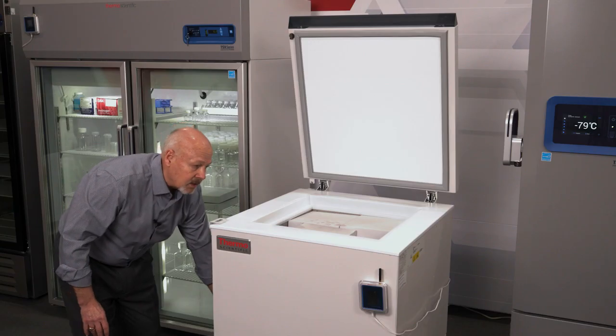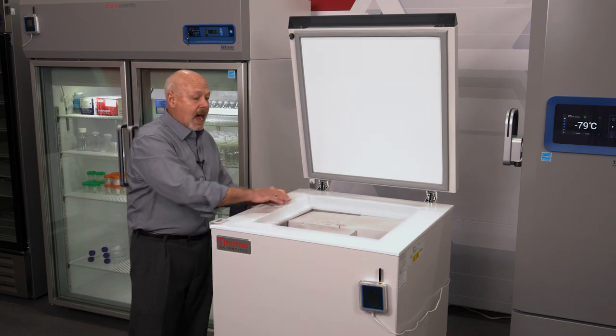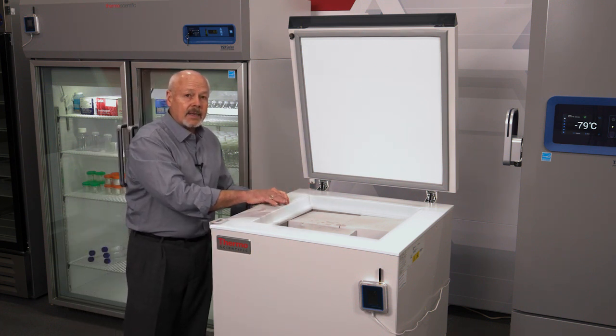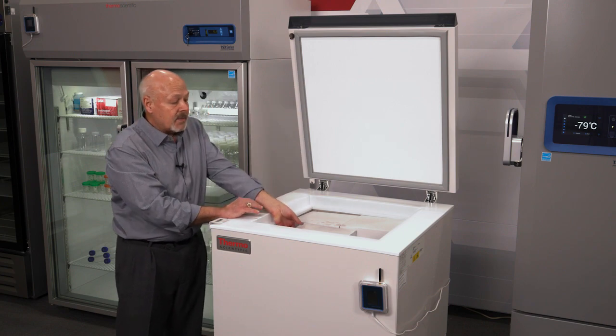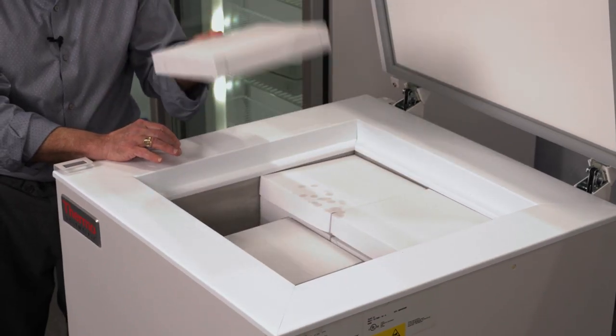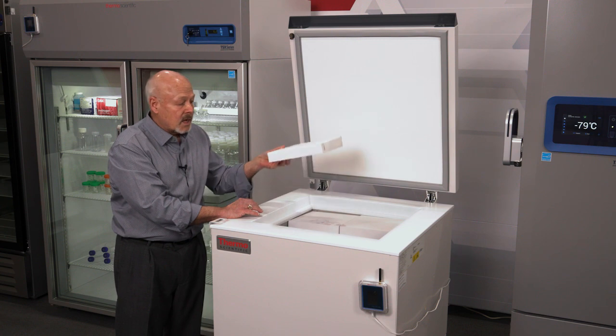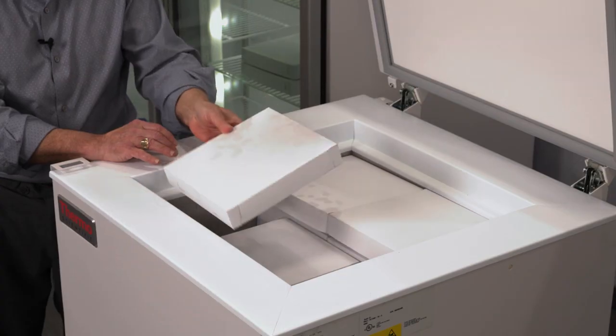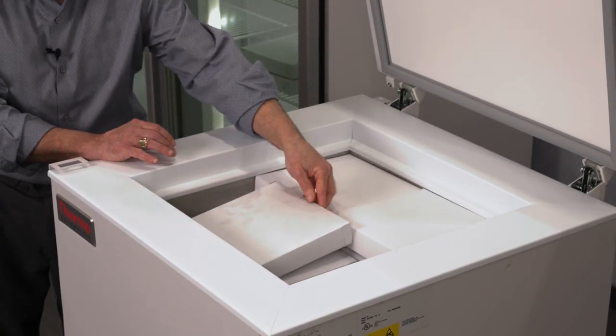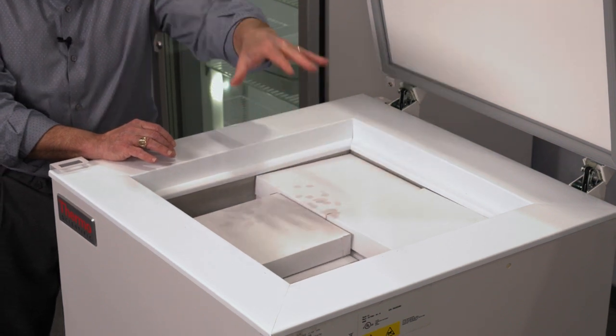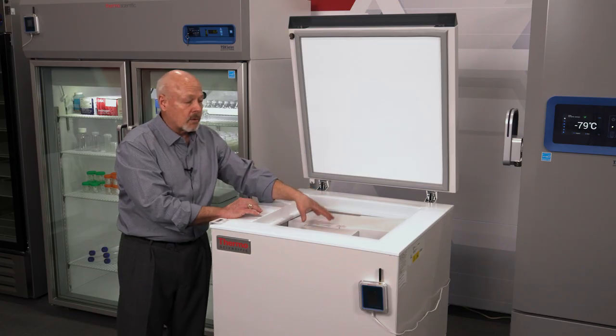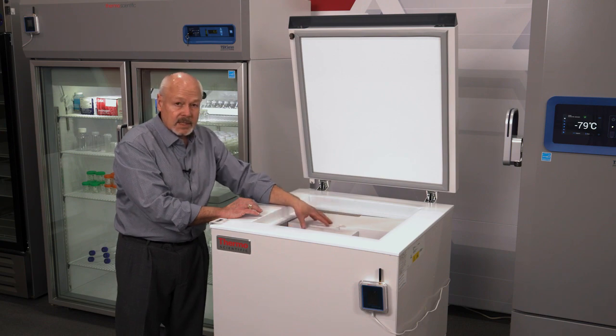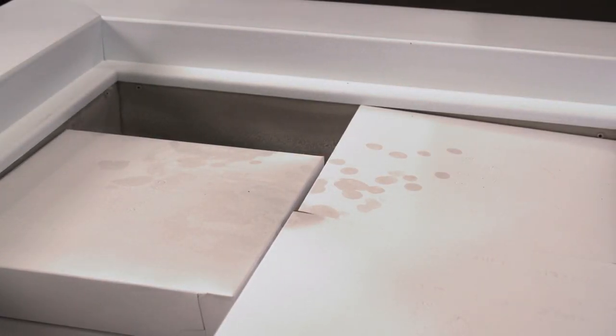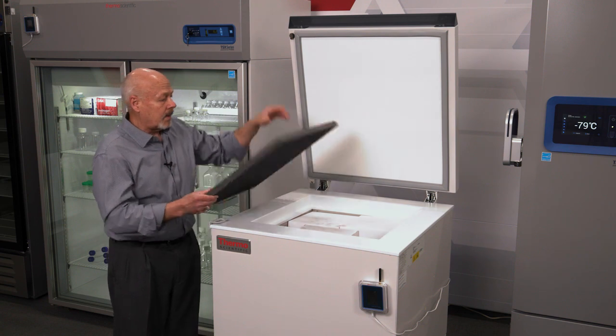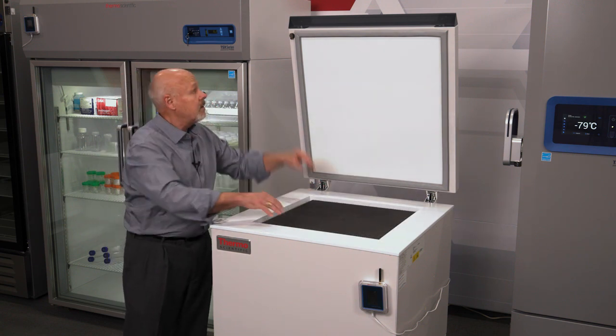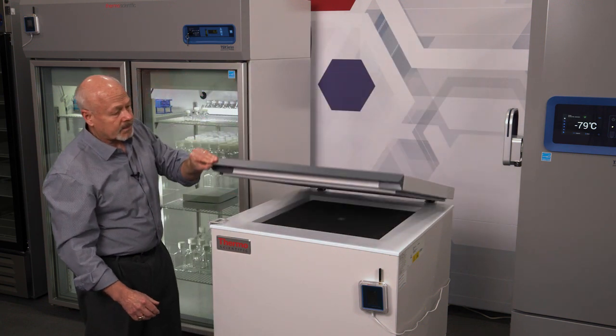And as we look inside the unit itself, you're going to see the size. It's actually 18.5 by 18.5 by 16.5. In this case, we're illustrating showing 30 of the Pfizer storage boxes that are able to be stored in this unit. That's over 35,000 doses of the Pfizer vaccine. Other cases, people might use racks or store other products within these units, but it's outstanding for storage of the Pfizer vaccine. And then to close the unit back up, I'm going to replace that inner lid, close the unit.